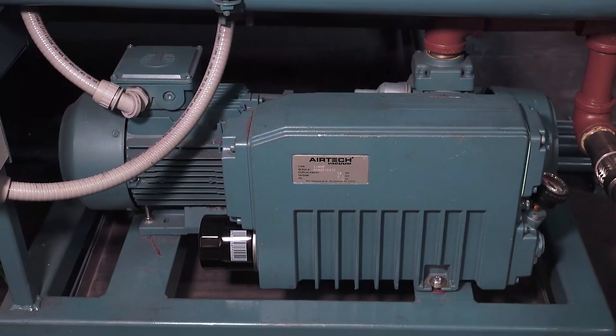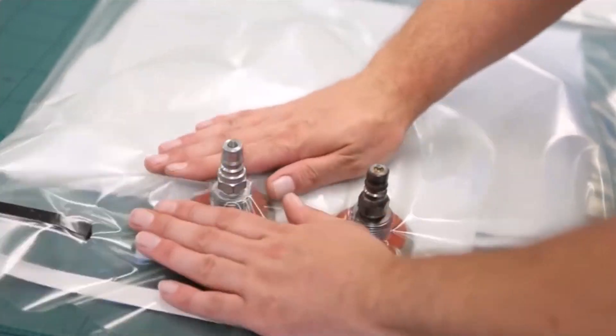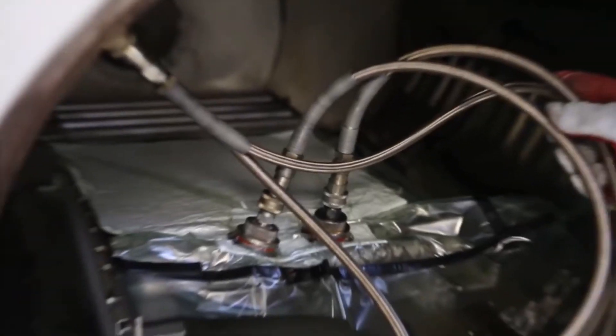To begin, let's get to know the vacuum pump. The vacuum pump on your Econoclave generates vacuum, or negative pressure, used to draw down vacuum bagged parts inside the autoclave. Without a well maintained vacuum pump, the vacuum level would degrade and your part quality will suffer.